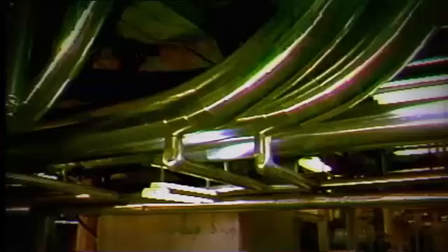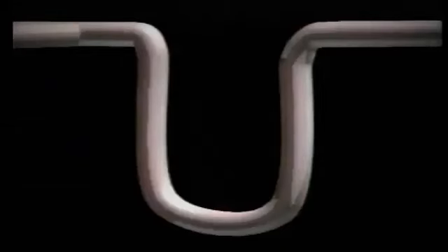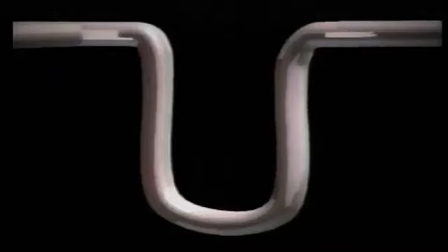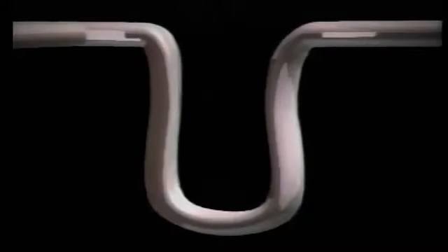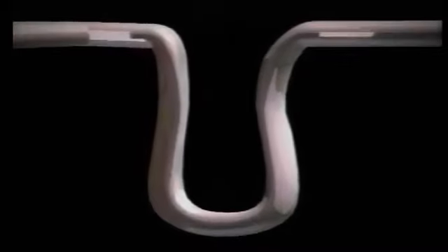The piping must undergo considerable expansion as its temperature is raised from, say, 200 to 1,000 degrees Fahrenheit. The run of pipework is designed with deliberate bends and turns to accommodate the expansion between two fixed points, that is, the boiler outlet and turbine inlet. The pipe hangers and supports are designed to be flexible and allow movement of the pipe under expansion forces.